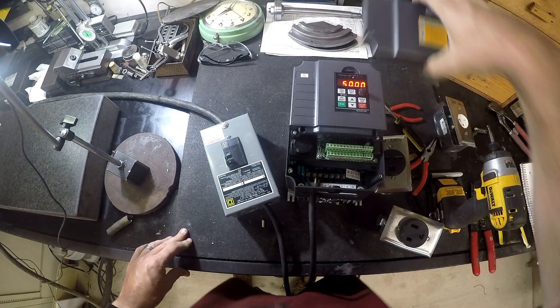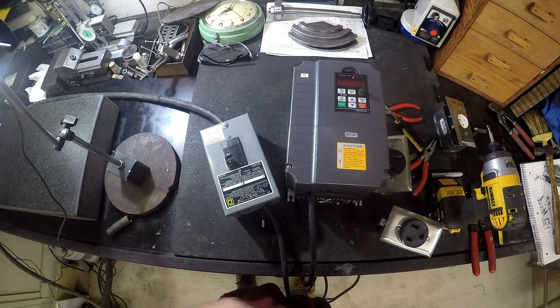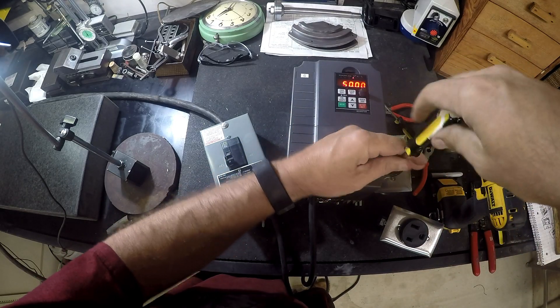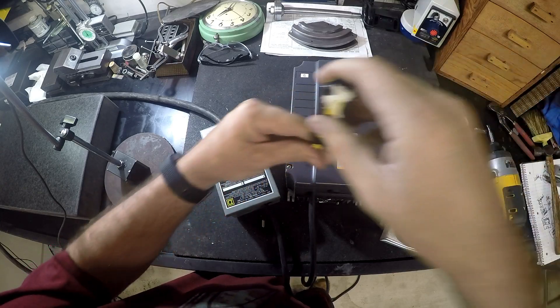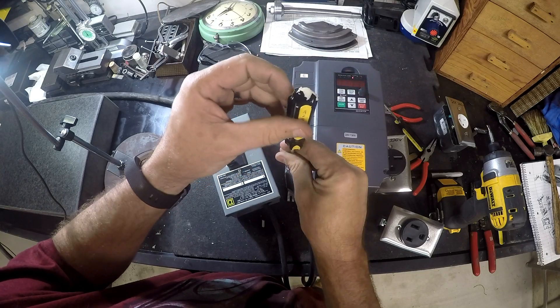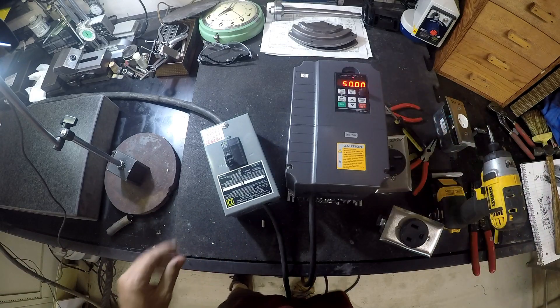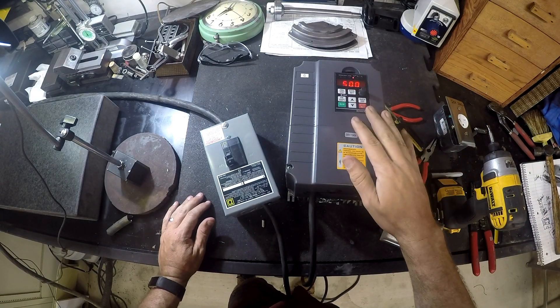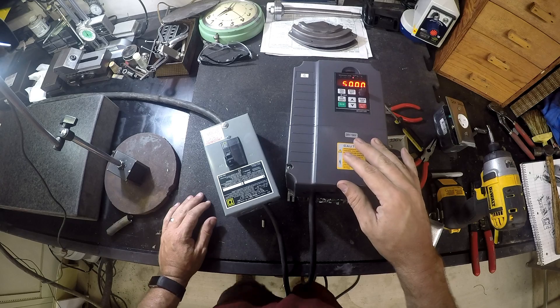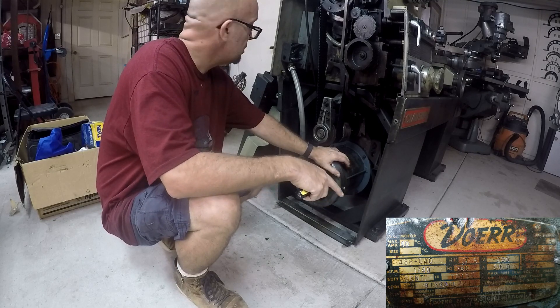I'm going to go ahead and cap this guy off. If you purchase one of these Huanyang VFDs, they always come set at 50 hertz, and most American motors are 60 hertz. So they'll always send you an email saying that's the first thing you're going to want to change — set it to 60 hertz. There are a few other settings in here I'll have to get set up, but at least I've got the power on. I've got a picture of the nameplate — I'll put that over here so you can take a quick look at it.